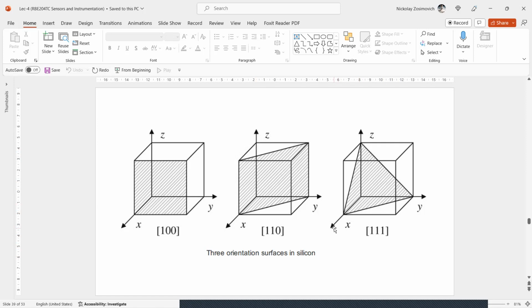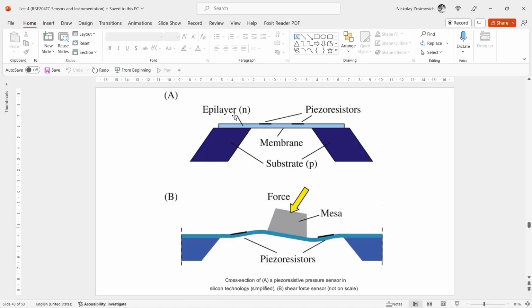So piezoresistors usually have an elongated shape to obtain direction sensitivity in a restricted area, as with metal strain gauges. To optimize sensitivity, the main axis of the resistor should coincide with the direction of maximal piezoresistivity on the membrane surface. The membrane deforms under a pressure difference, as you can see from figure A, or under applied force, as in the bottom figure B. Special design allows the measurement of both normal forces and shear force. Independent measurement of the force components is accomplished by proper positioning of a set of piezoresistors on the membrane.